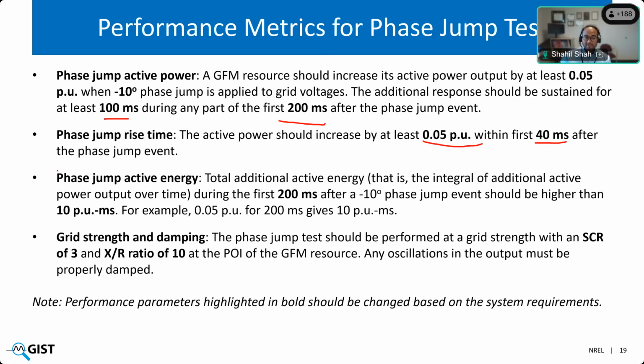Third is phase jump active energy, which is basically the area within the active power response compared to pre-disturbance level within the first 200 milliseconds. So again, we are trying to accommodate different shapes and different types of characteristics. We are really looking for how much energy the grid forming resource is contributing to the system immediately after a phase jump event. And then last is the grid strength condition.